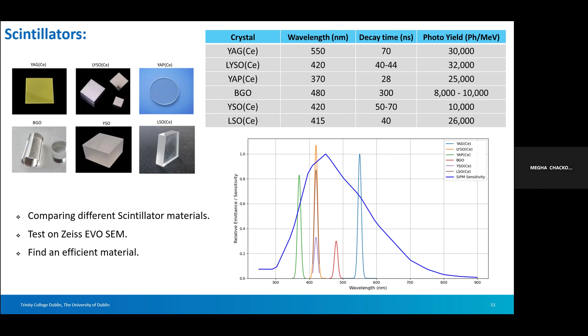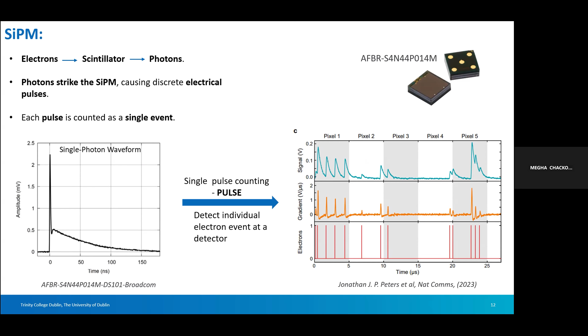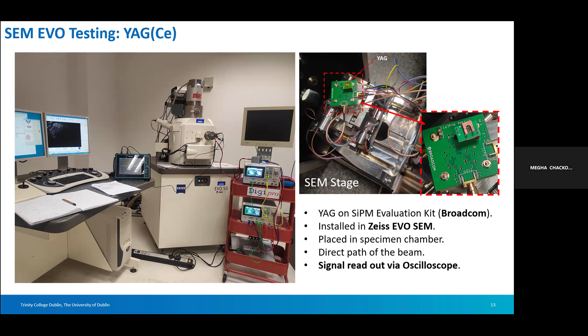So how can I make sure these scintillators are good enough? I also have to consider a silicon photomultiplier that is compatible with these scintillators. The wavelength of these scintillators should match the wavelength of the emission peaks of the silicon photomultipliers I'm using. Pulse counting is a technique where I can detect individual electron events at a detector. Before going directly to the TEM, I tested these scintillators on the SEM. I tested YAG with the silicon photomultiplier on the Zeiss Evo SEM, and we got a pulse where you can see we are getting single photon events.